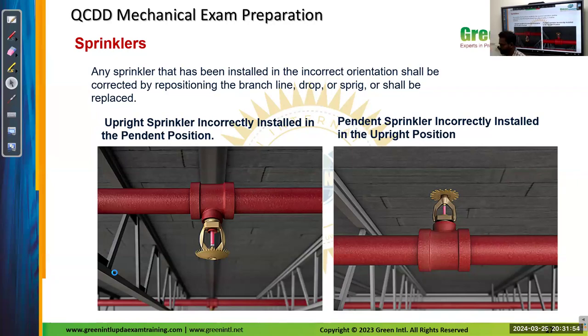Change with the same sprinkler or a different one? No, actually, the question last time they asked is, if there is a system, let's say 10 sprinklers are there, and you change one sprinkler, you don't have to do the test again. This means to replace the sprinkler. Yes, change this sprinkler with the same type. Yes, same type. If you are changing a pendant type, you have to use a pendant. In the exam, same type.